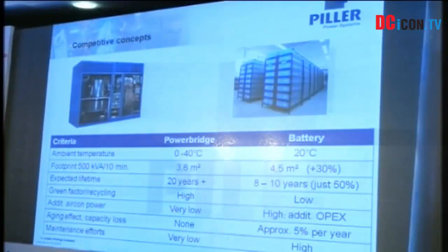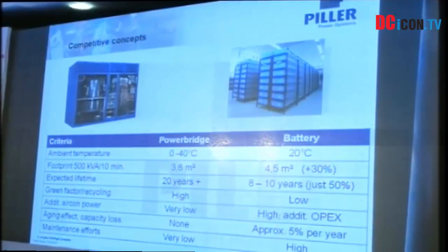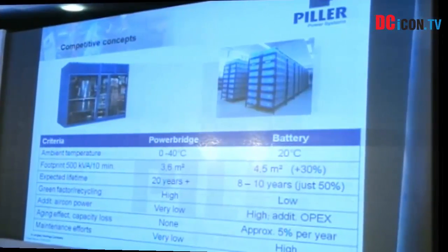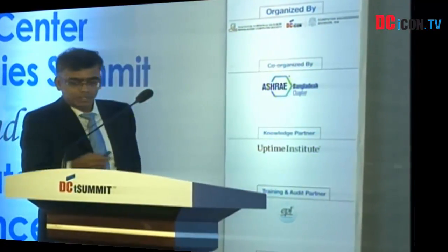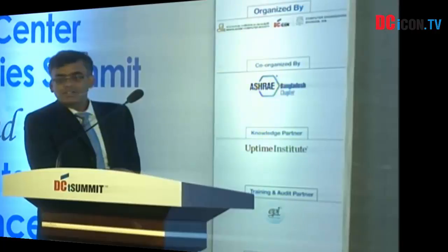Expected lifetime. Okay, here we have put 8 to 10 years. 8 to 10 years is for the most premium batteries available in the market, well maintained at 20 degrees or 18 degrees temperature. Whereas in general, when I visit many of my customers, they always say they replace their batteries in 3 years' time or 4 years' time. So you can imagine, here we are talking about a 20-year lifetime with no degradation, right? Whereas batteries degrade by time. Here you have a 20-year lifetime with no degradation of your power. The storage still remains the same, right from day 1 to day 20. No difference.